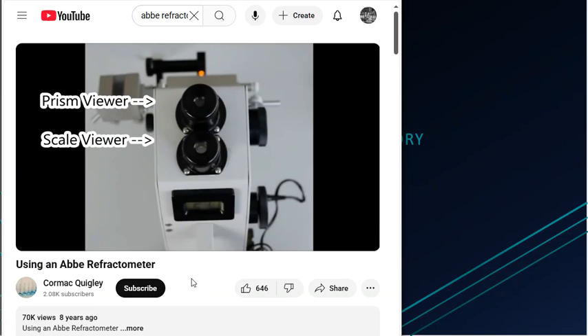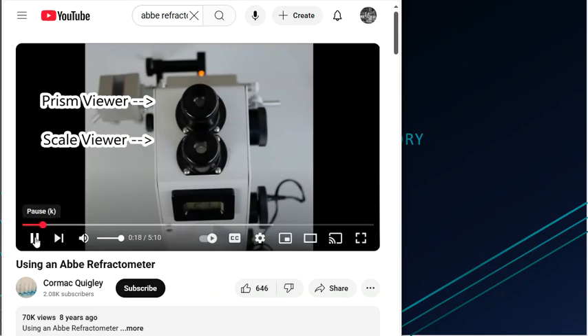On this model, there are two eyepieces, a prism viewer and a scale viewer. The prism viewer shows the light energy that's coming through, so you can see light and dark halves. And then the scale viewer is a meter that is associated with that light energy. Again, our version is one eyepiece, and there is a toggle switch that will allow you to go from one viewpoint to the next.